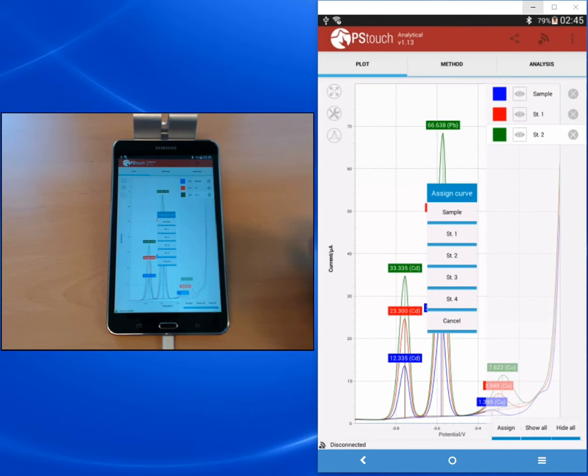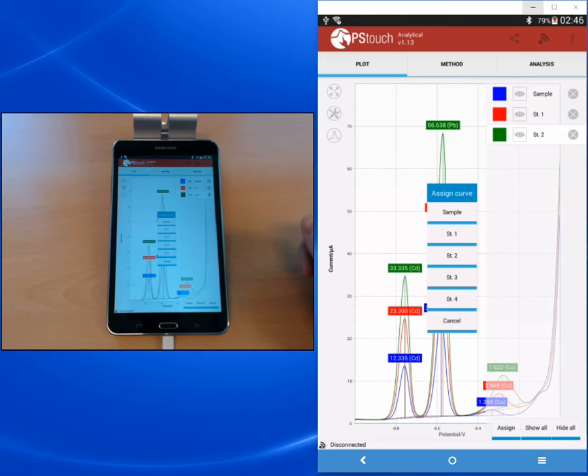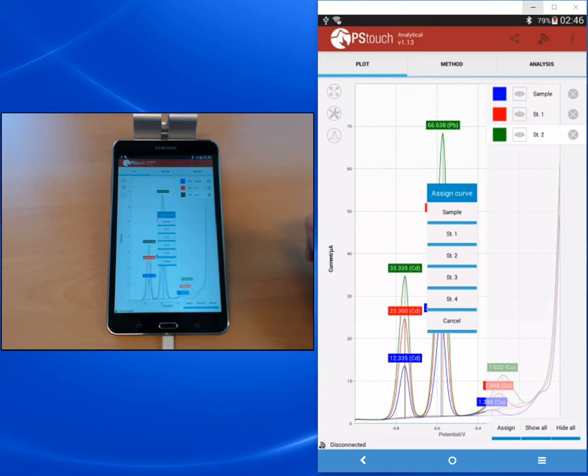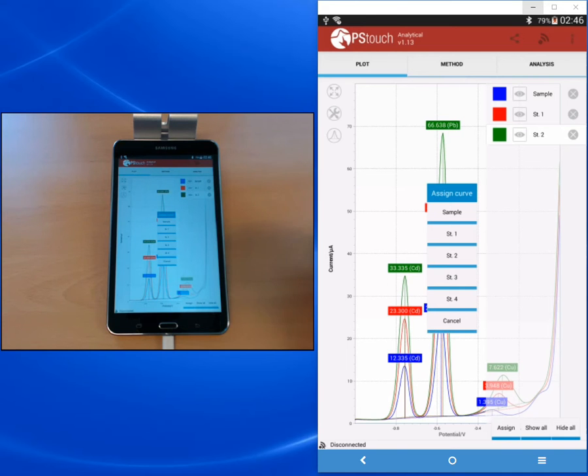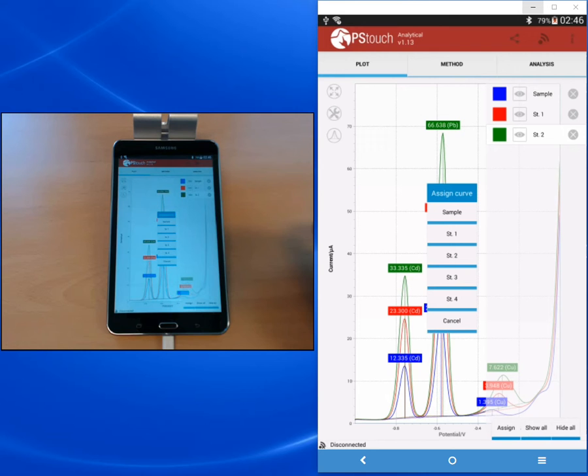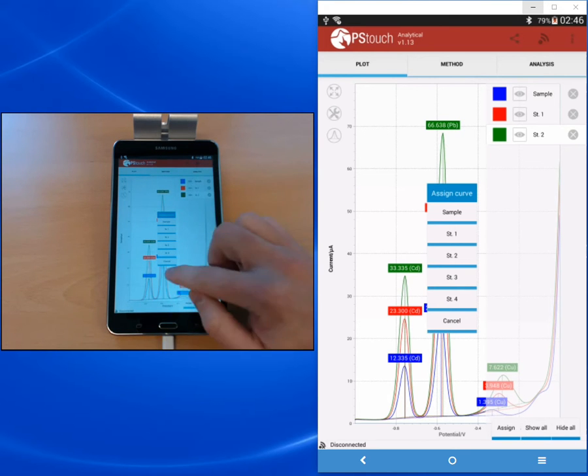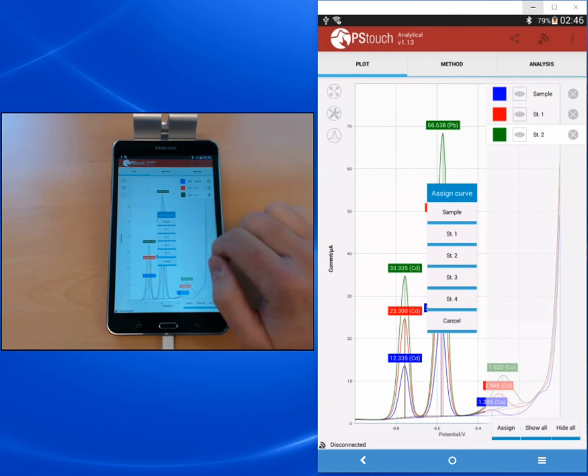With the correlation between the signal and the concentration from the calibration curve, you can determine the unknown concentration. The standard addition method is a method that you use when you are afraid that your matrix might influence your sensitivity. You use your sample and measure that first, then you add a fixed volume of your standard solution and make another measurement that will be standard one, then you add another fixed volume of your standard solution, repeat the measurement that's standard two, and then you can extrapolate everything.